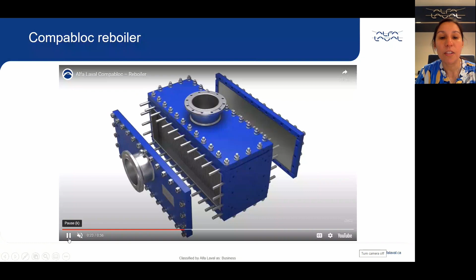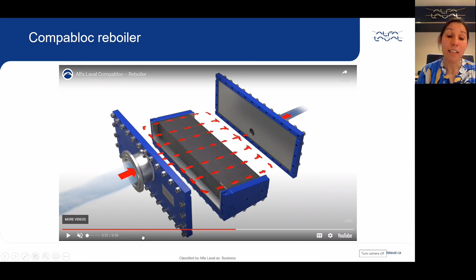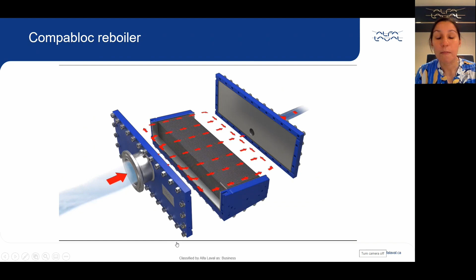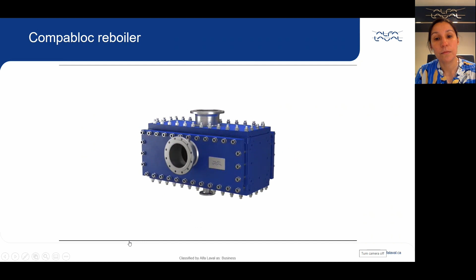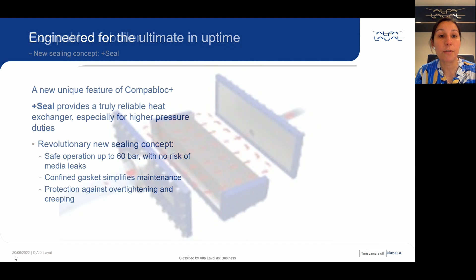And on the heating side, typically if you are using steam, we also have a single pass configuration for the steam side. Now, why don't we use multiple passes in a reboiler? We would if we have a liquid heating media. But for steam, since we are using the latent heat of the media, we don't need a multiple pass heat exchanger because we are not too concerned about temperature approach. We are just concerned about providing the most efficient path for latent heat to be transferred from one fluid to the other, and that would be our reboiler configuration.